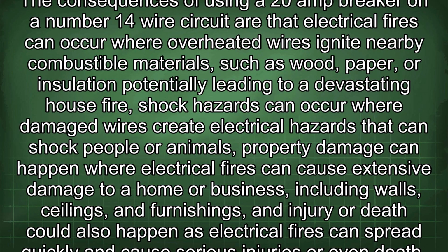The consequences of using a 20 amp breaker on a number 14 wire circuit are that electrical fires can occur where overheated wires ignite nearby combustible materials, such as wood, paper, or insulation, potentially leading to a devastating house fire. Shock hazards can occur where damaged wires create electrical hazards that can shock people or animals. Property damage can happen where electrical fires can cause extensive damage to a home or business, including walls, ceilings, and furnishings, and injury or death could also happen as electrical fires can spread quickly and cause serious injuries or even death.